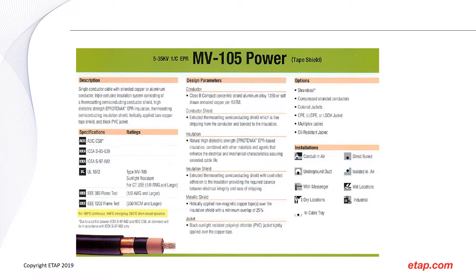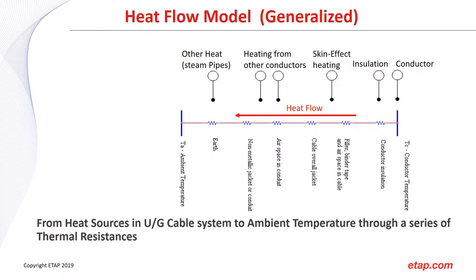Here is a typical data sheet for an EPR MV 105 power cable — for example a 35 kV cable — which provides the maximum TC temperature. This type of data sheet also typically provides an ampacity, but that ampacity is usually under very confined restrictions, such as a 2×2 underground installation, and doesn't take into account many factors. To generalize the heat flow model, the heat flows from the conductor temperature through a series of thermal resistances.